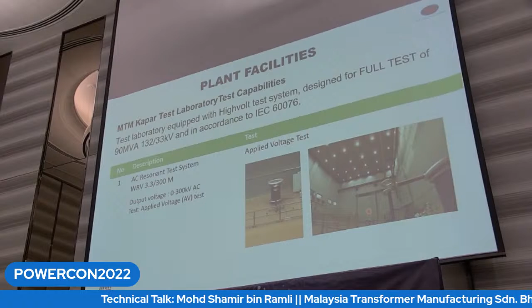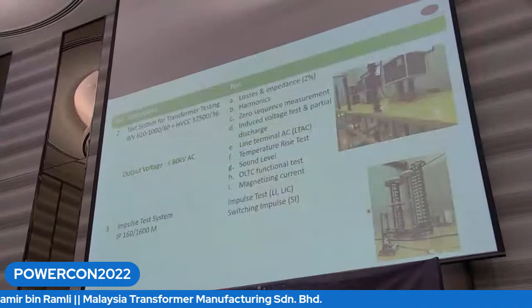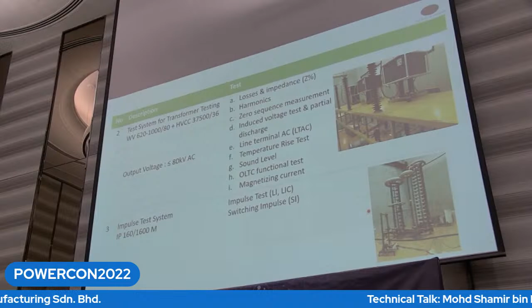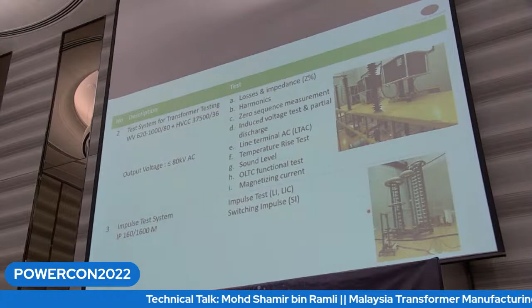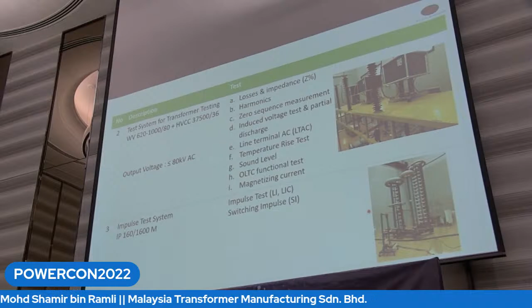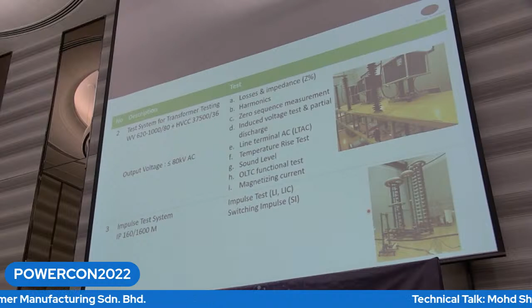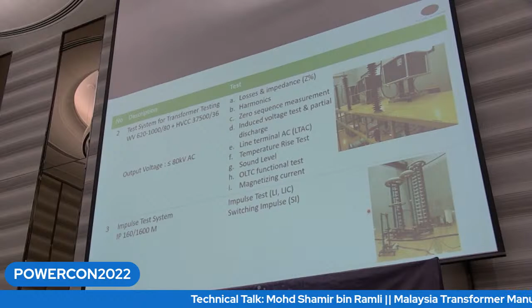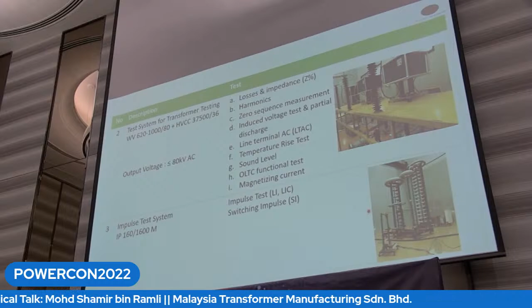It is equipped with an AC resonant test system for applied voltage tests, and also a test system for transformer testing which can carry out loss measurement, harmonic zero sequence impedance, line terminal AC temperature rise and magnetizing current, among others. We can also conduct the impulse test system for lightning impulse, switching impulse, and chopped wave. This is why we say this is the only high voltage laboratory with such facilities in Malaysia.